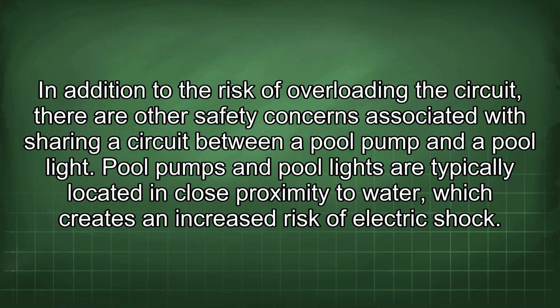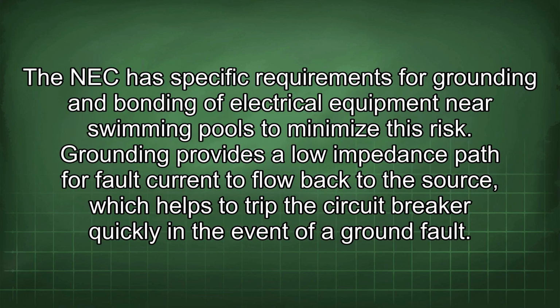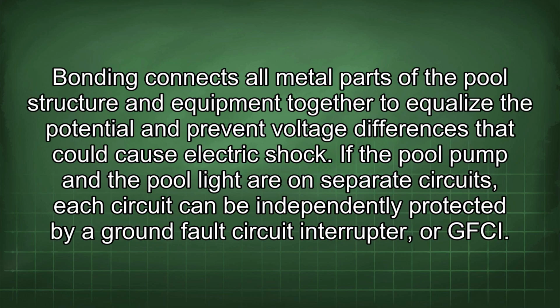In addition to the risk of overloading the circuit, there are other safety concerns associated with sharing a circuit between a pool pump and a pool light. Pool pumps and pool lights are typically located in close proximity to water, which creates an increased risk of electric shock. The NEC has specific requirements for grounding and bonding of electrical equipment near swimming pools to minimize this risk. Grounding provides a low impedance path for fault current to flow back to the source, which helps to trip the circuit breaker quickly in the event of a ground fault. Bonding connects all metal parts of the pool structure and equipment together to equalize the potential and prevent voltage differences that could cause electric shock.